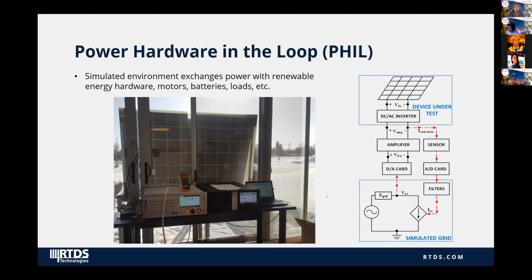The next question is from Dr. Lidula: is it possible to test any user-built protective relays? Of course, you can test user-built protective relays. As I mentioned during my presentation, simulators support different types of interfaces. You may use analog interfaces to connect to a protective relay using the conventional approach, providing low-level voltages. If your relay voltage level is within plus or minus 10 volt peak to peak, you can directly feed those signals to the DSP board of your protective relay.